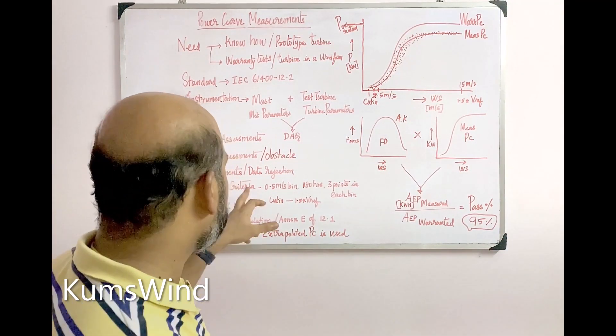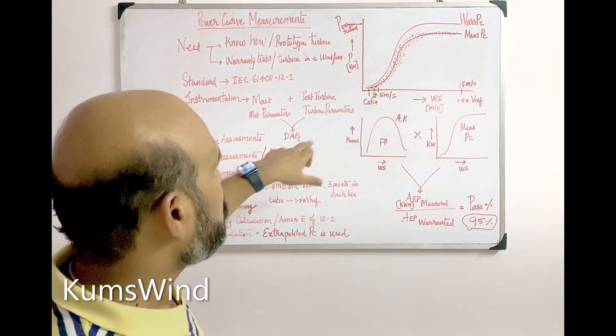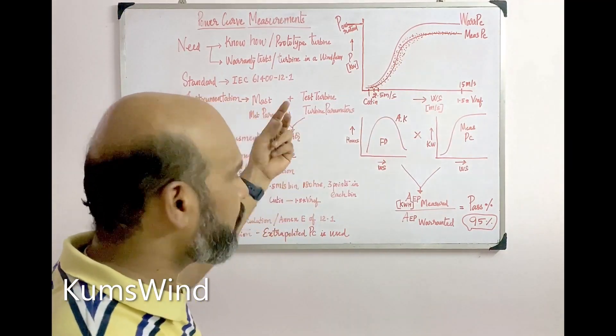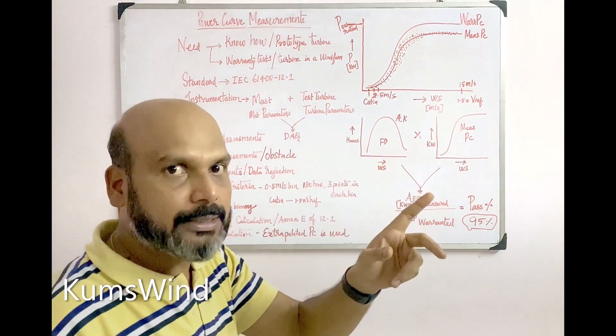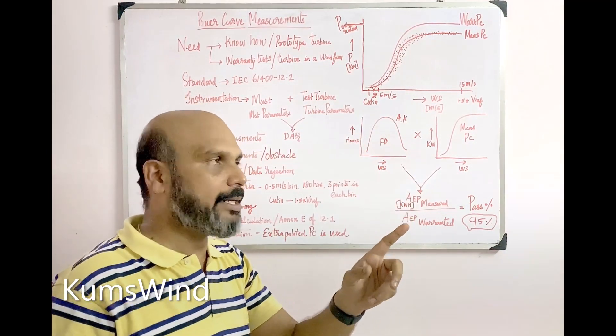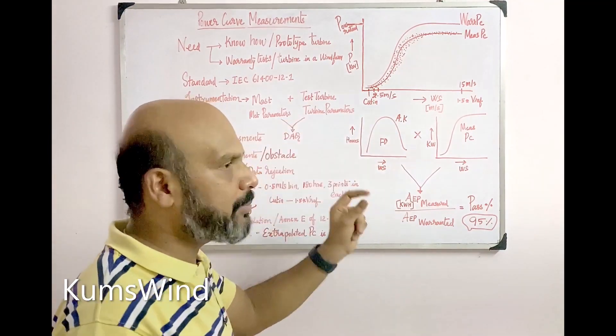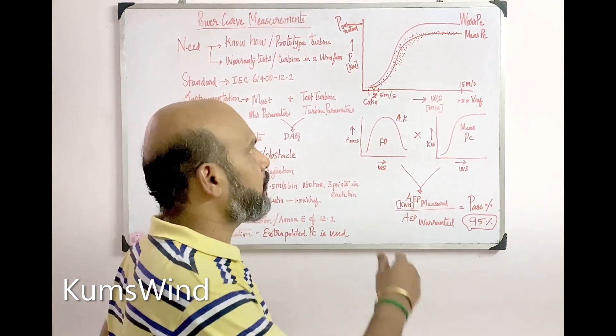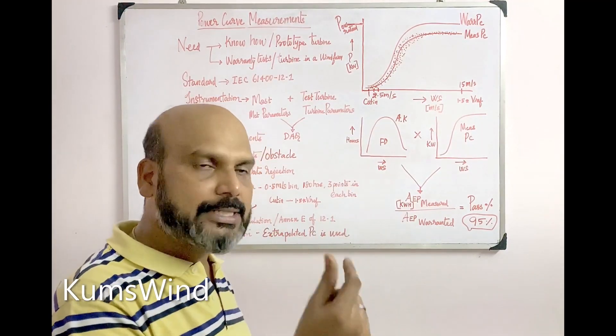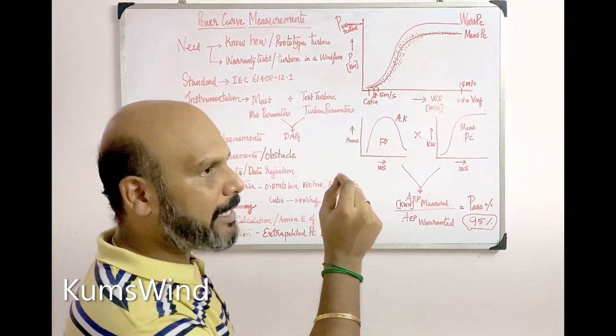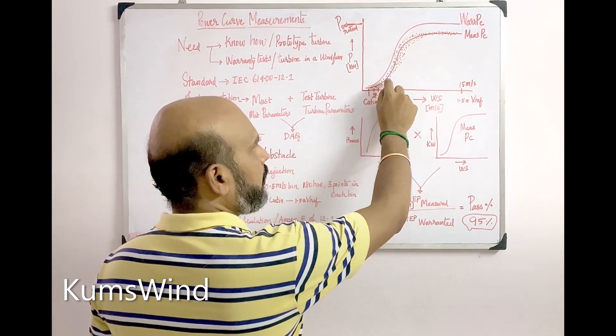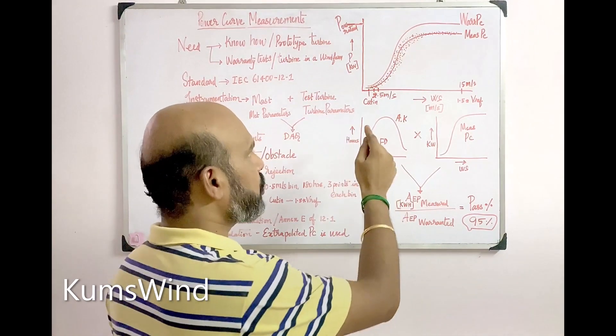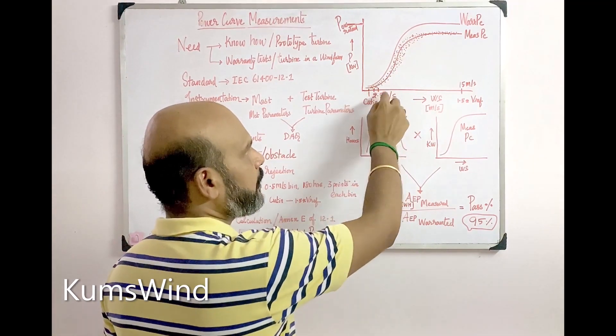The database fulfillment criteria defines how a power curve measurement is considered complete. The sampling frequency required by IEC 12-1 is 1 Hz — one sample per second per parameter. Every 10 minutes you will have 600 data points, and one average is taken for those 600 points. Each point on the scatter plot represents a 10-minute average.